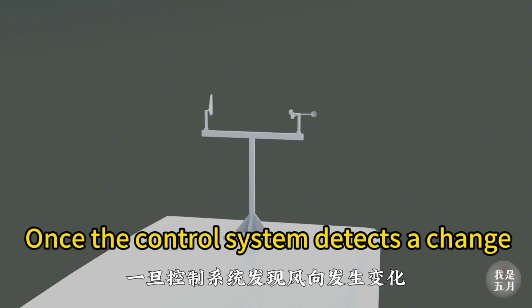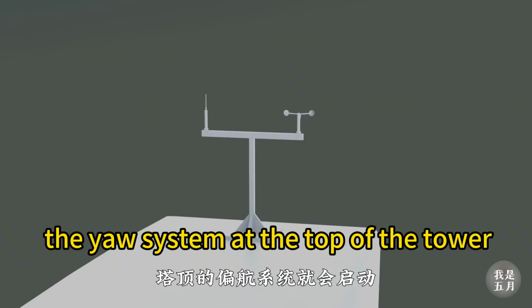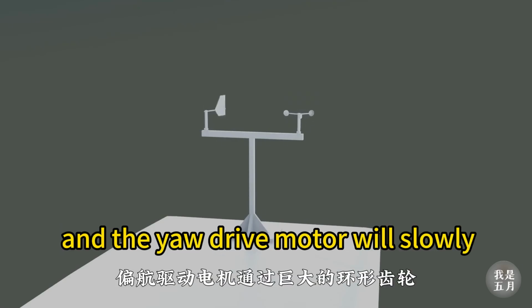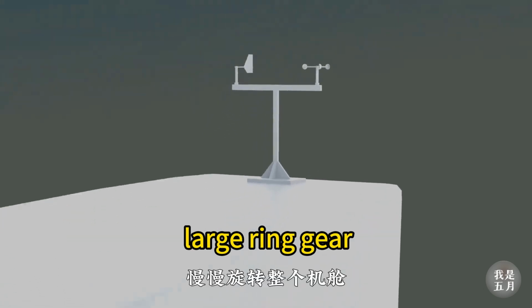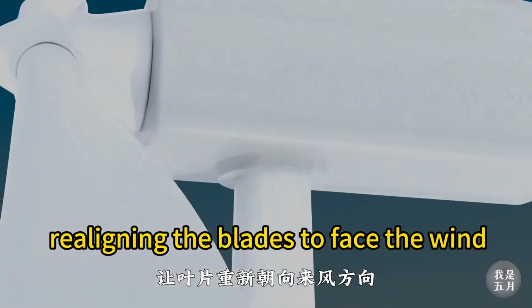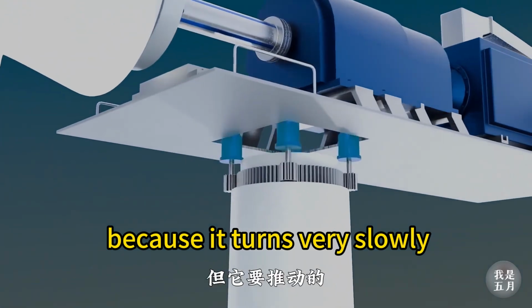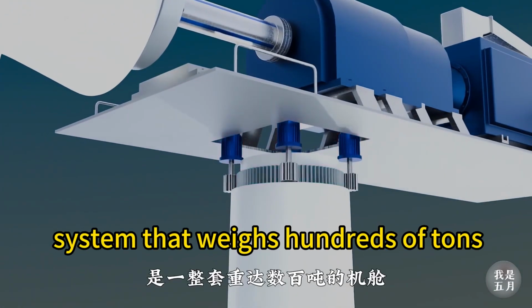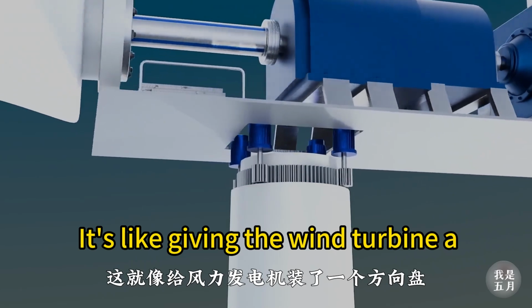Once the control system detects a change in wind direction, the yaw system at the top of the tower will activate, and the yaw drive motor will slowly rotate the entire nacelle through a large ring gear, realigning the blades to face the wind. You can't see it moving, because it turns very slowly, but it has to move a nacelle and rotor system that weighs hundreds of tons. It's like giving the wind turbine a steering wheel.